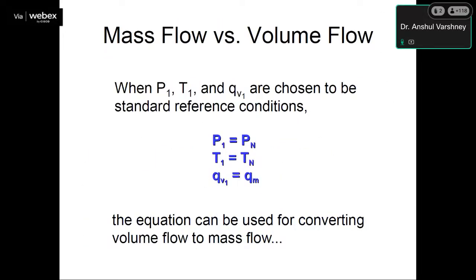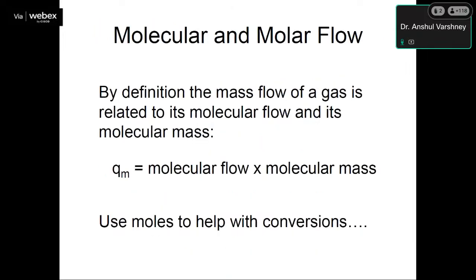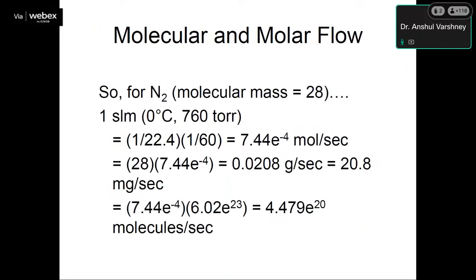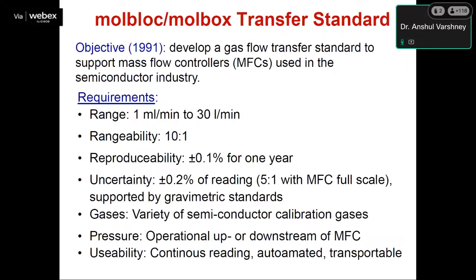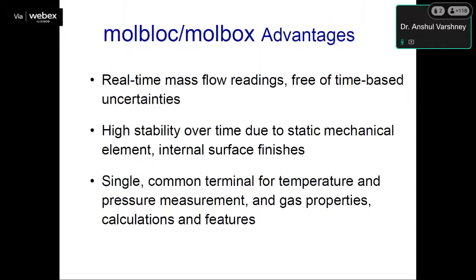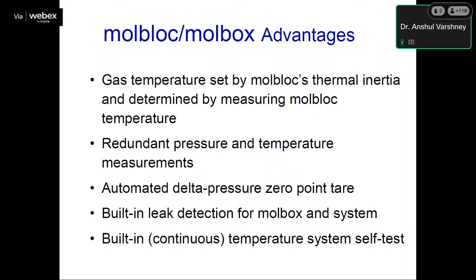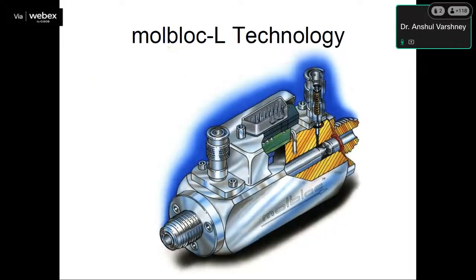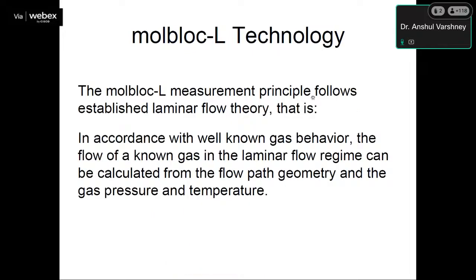Basically, now I am coming directly to the standards which we are using at NPL. We are using the Molbloc-Molbox transfer standard for calibration of gas flow systems. We have a range from 1 SCCM to 2000 liters per minute. This is basically the Molbox terminal, which works on the principle of differential pressure. We measure upstream pressure and downstream pressure, and with the help of these, the flow rate can be calculated.